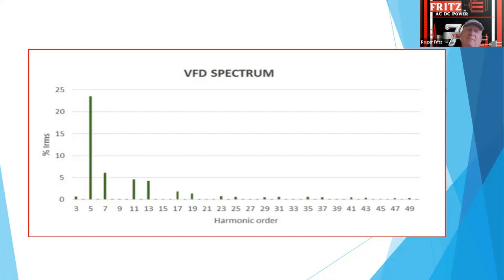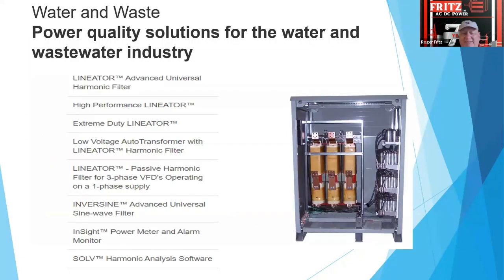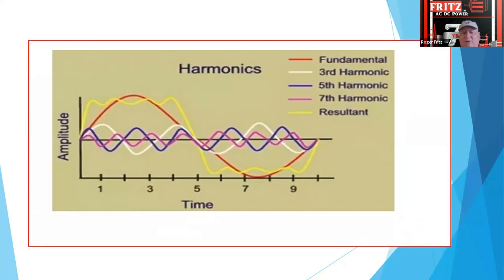A lot of people say, oh well, I put a VFD in, it's got proper inputs and it's got a line reactor on it. But again, it's all an LC circuit, with both inductive and capacitive loads going on out there. And that's why I like the Fluke meter, because it allows us to actually see what's really going on.